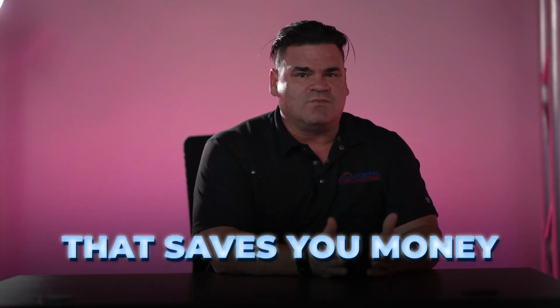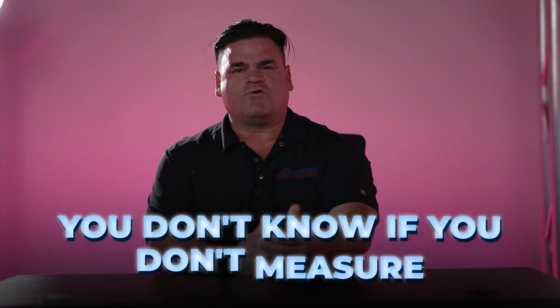Maybe we can go down half a ton. We've seen situations where we can go down a whole ton of air, and that saves you money. We've also seen systems where it's undersized, and we have to go up half a ton or a ton. But you don't know if you don't measure, if you don't perform the heat load calc.